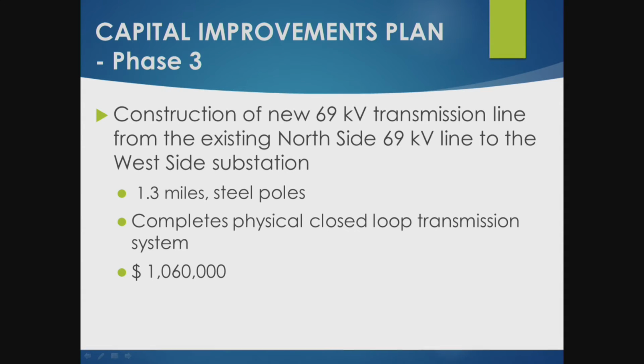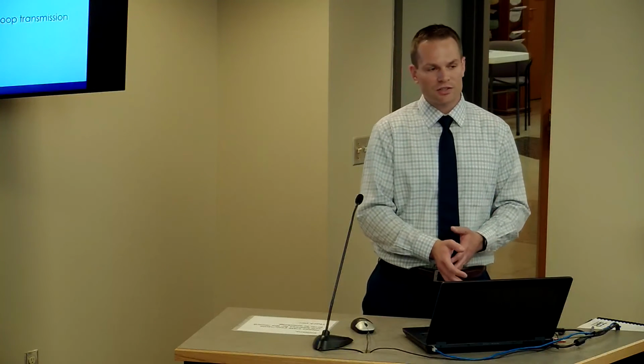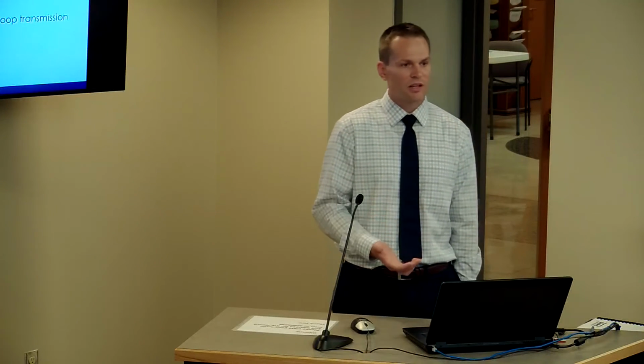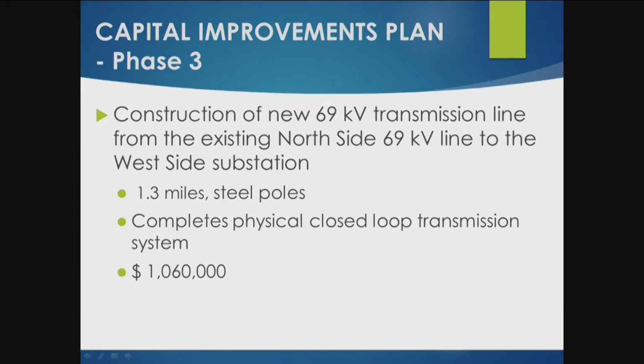Phase three consists of basically completing the loop. Once we get phase one and two done, then you're kind of tying in some loose ends. You're getting pretty close, you have a physical loop for the most part, with the exception of an additional tie to the existing north substation, the line feeding the existing north side sub to what would be the west line, what we could call it. So you're basically connecting a loop around the whole system. There's some breaker upgrades, some relay upgrades included there. About $1 million more after the heavy investment, then you're getting close to that closed loop system.